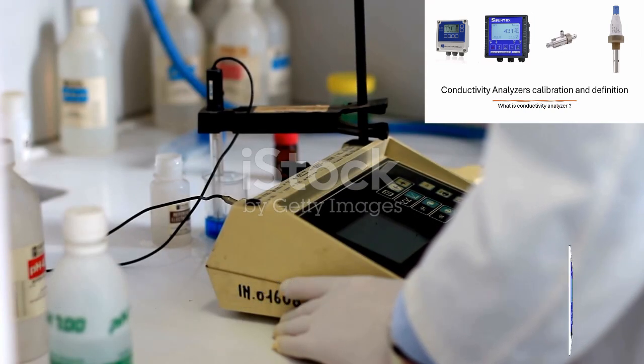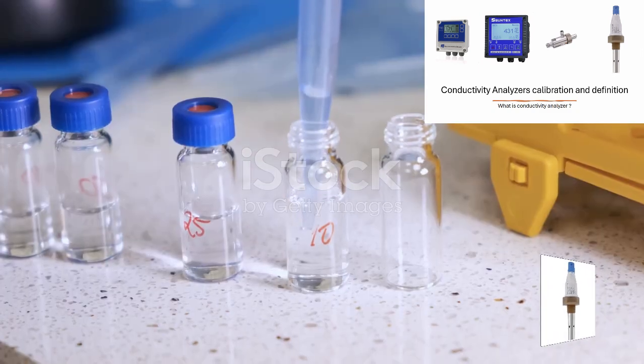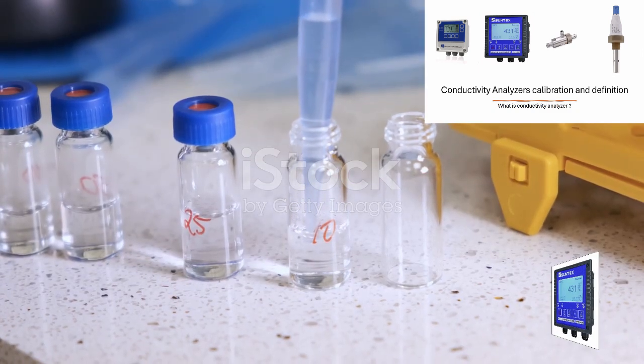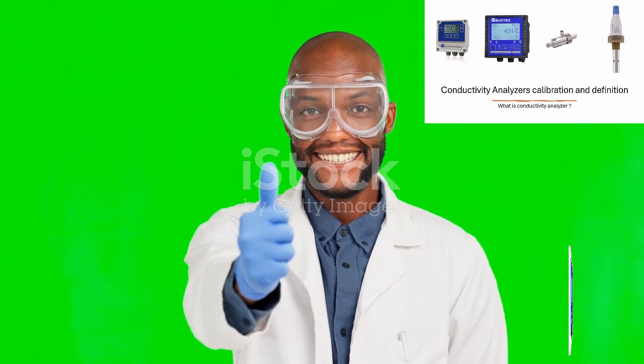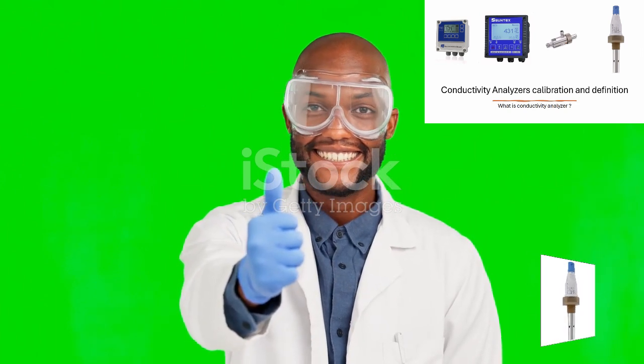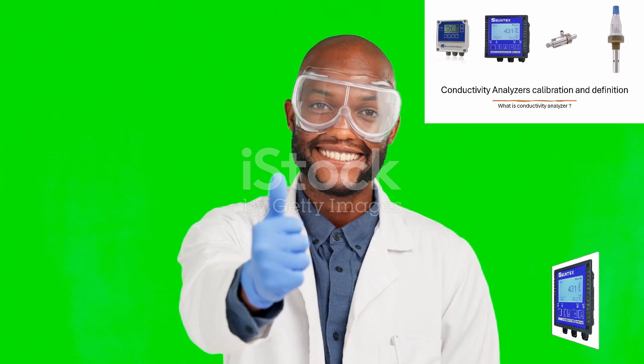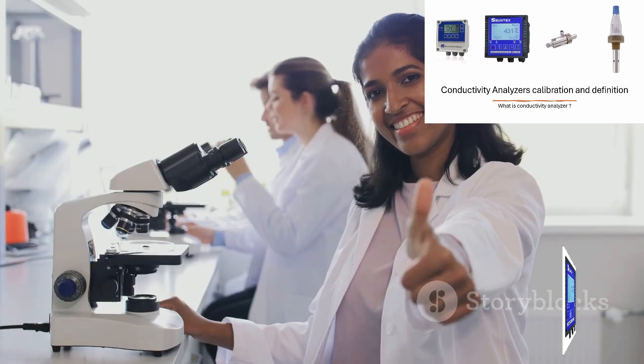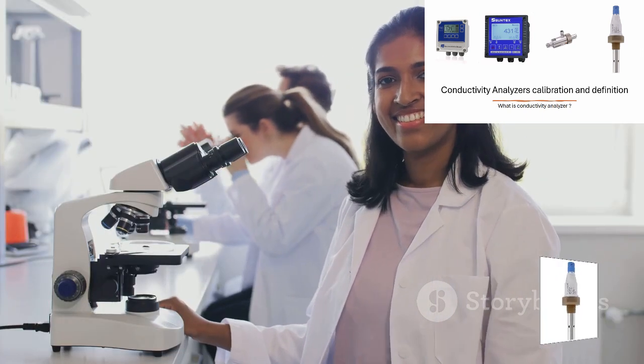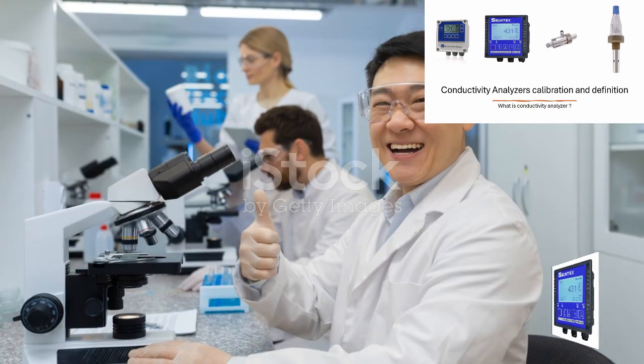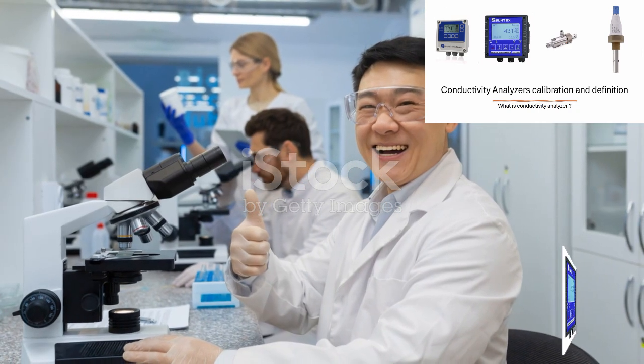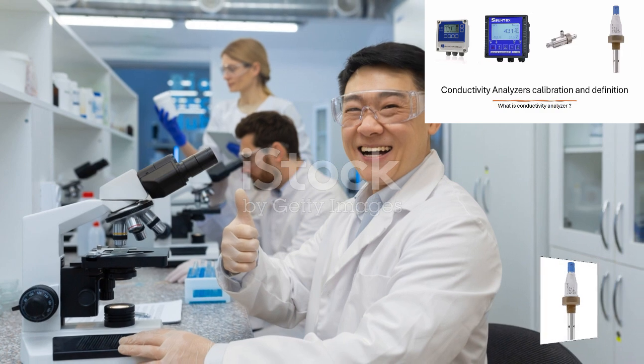All right, it's time to get hands-on. Let's walk through the calibration process using our standard solutions. It's easier than it sounds, I promise. The first step is to wake everything up. Turn on your conductivity meter and connect the sensor probe securely. Let the meter warm up for a few minutes as the manufacturer suggests. This helps stabilize the electronics for a more reliable reading.